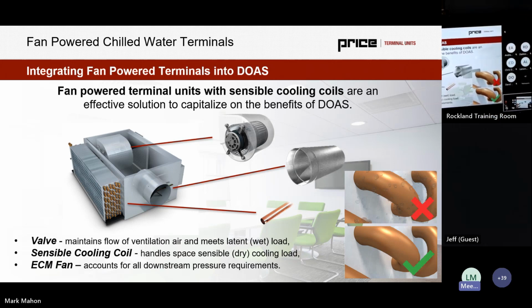So other high level things, they have a lot of capacity localized into one piece of equipment, up to 36 MBH. They come in a variety of sizes and configurations with a number of different accessories that can help with very large zones and zones that are very variable in their occupancy. So it is a really good exterior component. It's really good for exterior large zones. Of course, it can be utilized throughout a building, but if we look at a DOAS system, typically the larger the zone and the higher the loads, the more we'd maybe pivot towards this product.